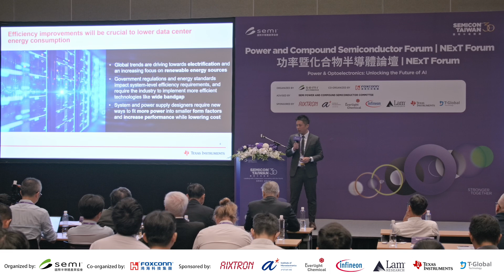We see about 80% efficiency from this entire power path. A bit more on this: the architecture started developing in the 1990s, but has been the industrial standard for server power delivery for decades. A larger portion of power delivery still adopts this configuration, from grid to mechanical transformer to 480 volt AC, going all the way through the server, and connecting through a UPS to provide battery backup and stabilized AC power supplying into the server rack. Inside the server rack, the AC power is rectified and stepped down to 12 volts, then goes to the multi-phase power to enable the CPU at the server.